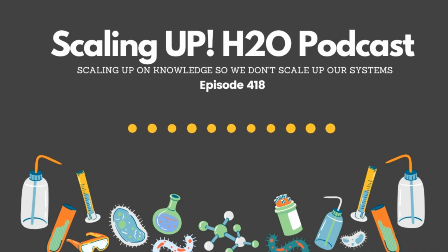So, why would somebody choose an organic phosphate over an inorganic phosphate? Well, I think it's situational. It goes back to the toolbox thing. I'll start off actually with the opposite. I think inorganic phosphates and polyphosphates are going to be the most cost effective and possibly the most effective corrosion inhibitors when used in combination and used properly, of virtually all the tools that we have available to us.